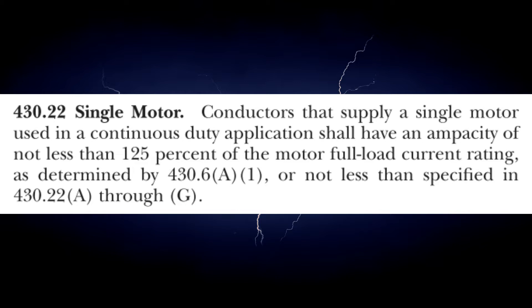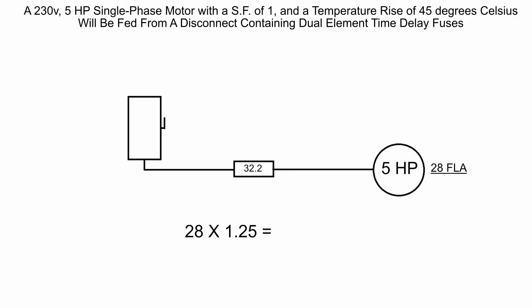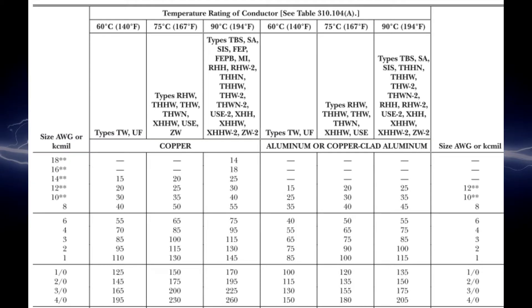Anything in a commercial facility will be a continuous duty application. One of the few examples that wouldn't qualify would be like a garbage disposal in a house. When taking these exams and you get motor calculations, 99.9 percent of all the exams in this country are going to use continuous duty applications. That's basically the testing standard. We'll take our full load amps at 28 times 1.25 or 125 percent and we will come up with 35 amps. That's what we're going to factor and use in order to size our wire, which we will do over in 310.15(b)(16).